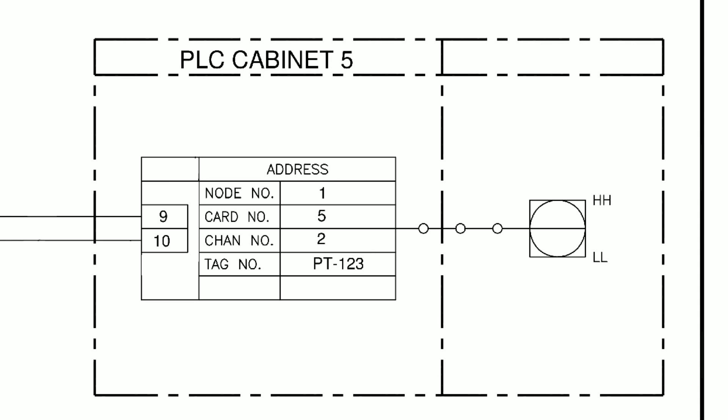It's also worth noting to the right of this information we have the symbol of a square with a circle within it and a line through. This denotes the PLC's internal connection from a software point of view to the DCS or SCADA and shows that there is a high high alarm and a low low alarm. These are the conditions that will be shown to the operator and may have automated executive actions such as shutting certain parts of equipment off or putting the plant into a safe condition.